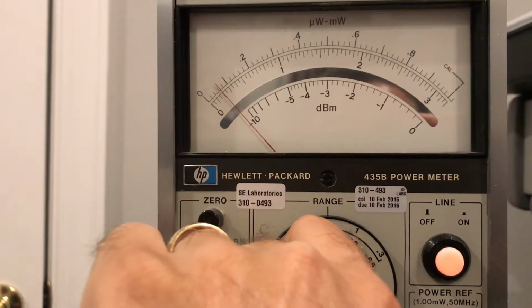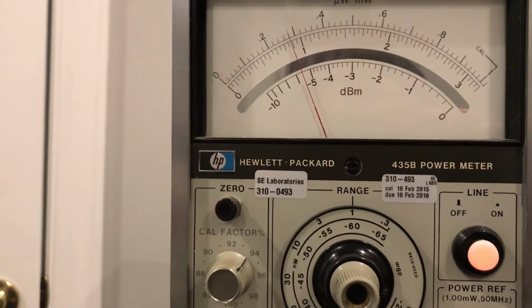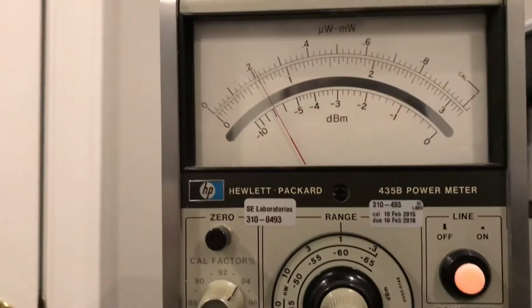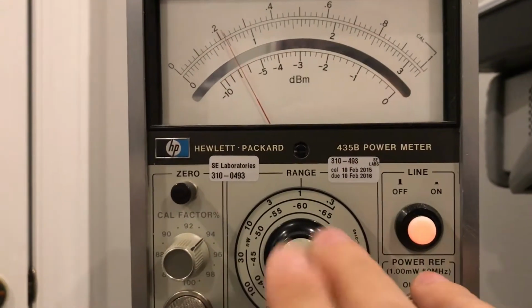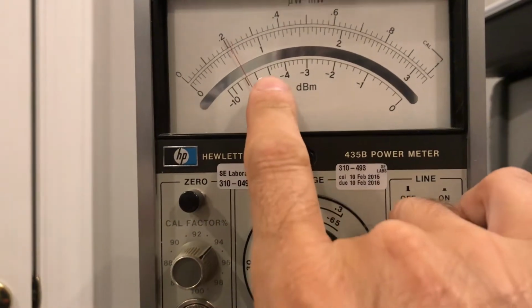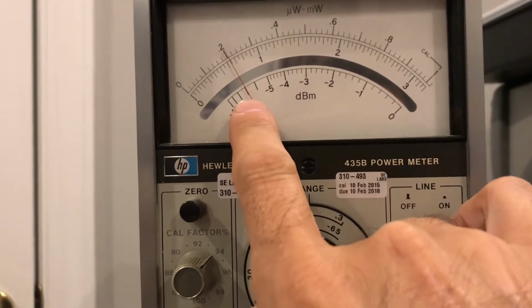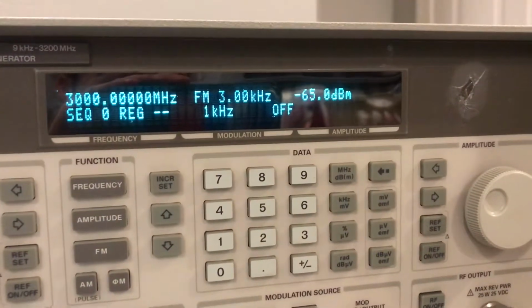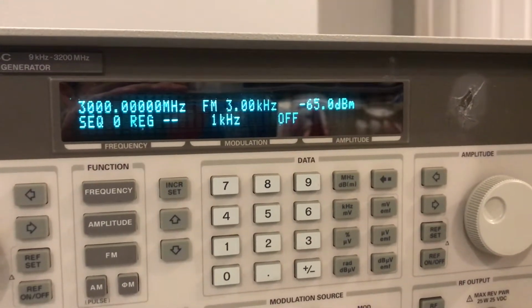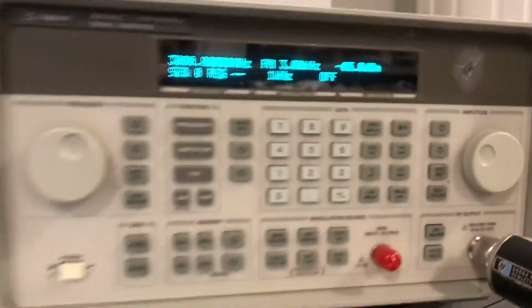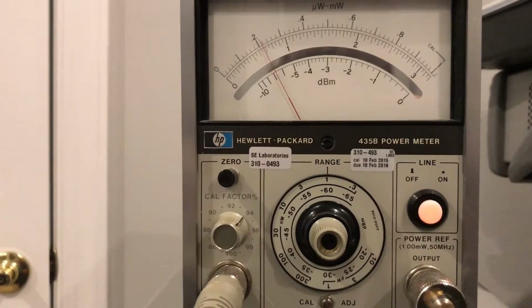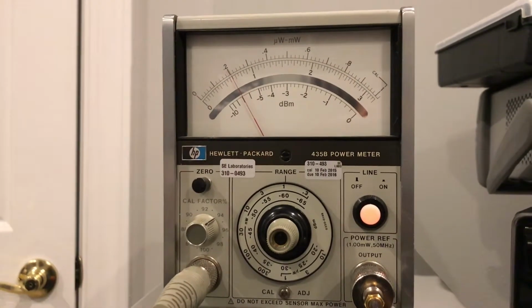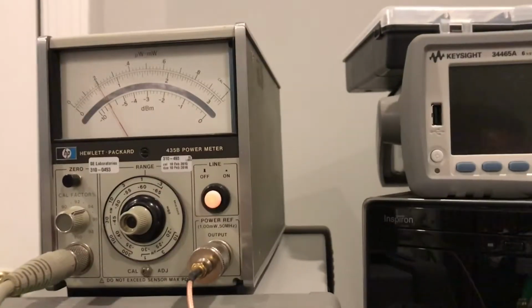Alright, and now we're going to start getting into where the sensitivity is really sensitive up here. So we're looking at negative 65, 66, 67. So the power meter is showing negative 67, and our signal generator is showing negative 65 dBm. But like I said before, with these sensors, about minus 65 dBm is really the floor as far as where you're going to get any noticeable change.